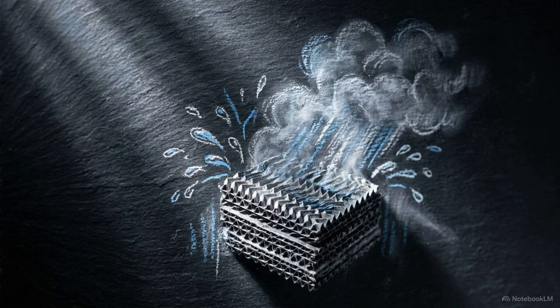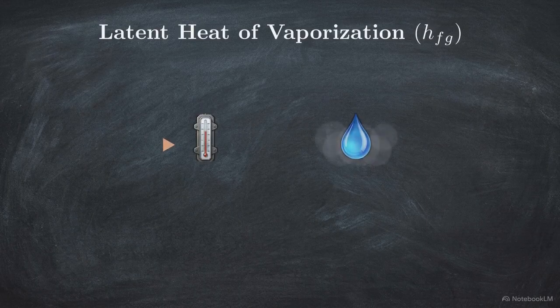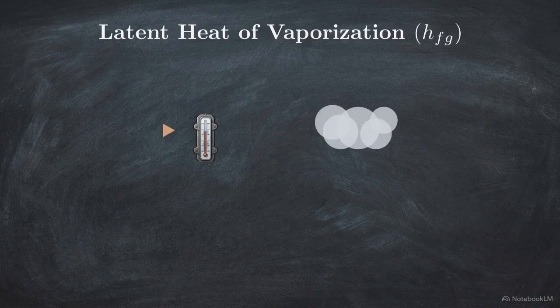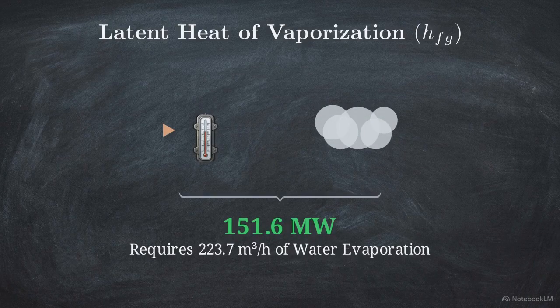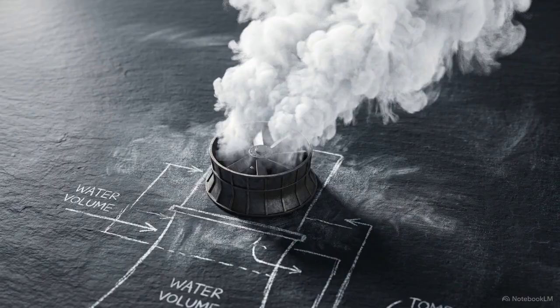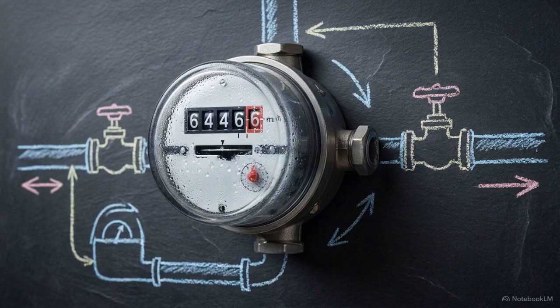Here, hot facility water flows over fill media, exposed directly to the outside air. The latent heat of vaporization dictates exactly how much water must evaporate to shed the 151.6 megawatt load. This process requires evaporating 223.7 cubic meters of water per hour. Factoring in blowdown, the open wet tower requires 6,446 cubic meters of makeup water daily.